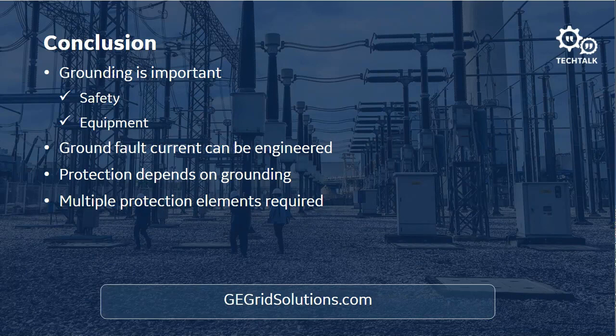It also controls the transient overvoltages due to arcing during ground faults on ungrounded systems, relieving stresses placed on the insulators, which might or might not be designed to handle those phase-to-phase voltage stresses. We can locate ground faults when they do happen with the various protection measures we discussed, from the voltage methods to the current methods, depending on whether it's high impedance or low impedance.